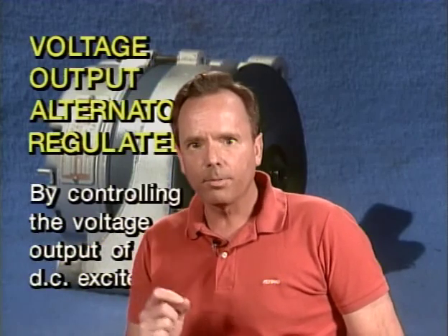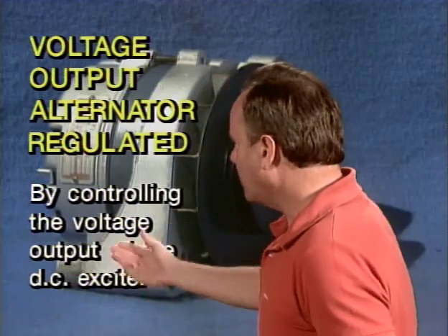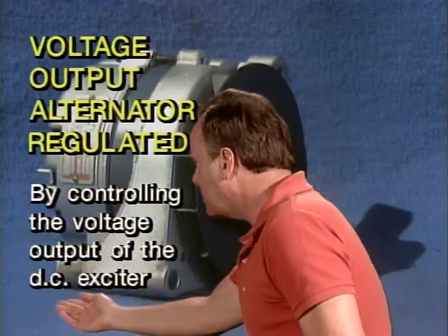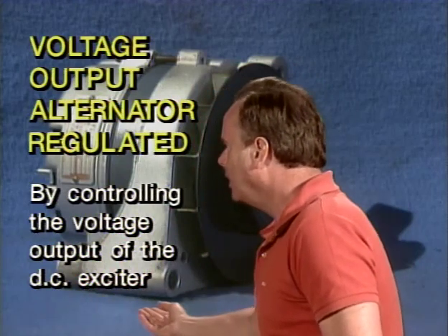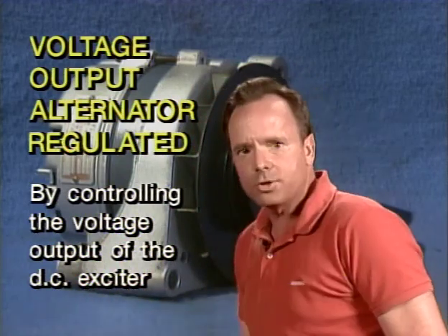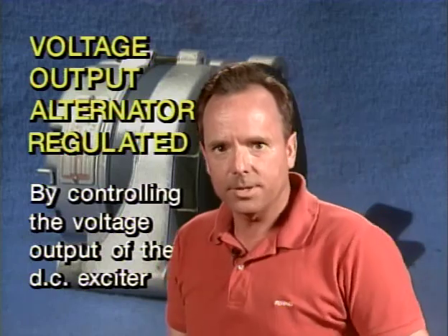All right, let's take a look at the voltage output of an alternator, how it can be regulated. And the answer is by controlling the voltage output of the DC exciter. That's another way of saying the field. So you regulate the voltage by regulating the field, or the DC exciter.